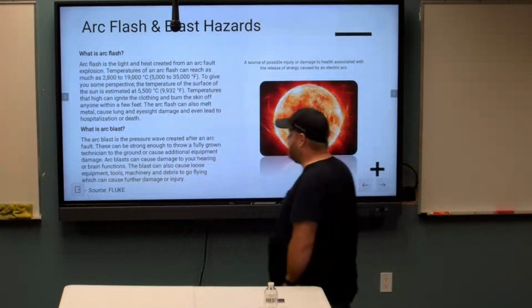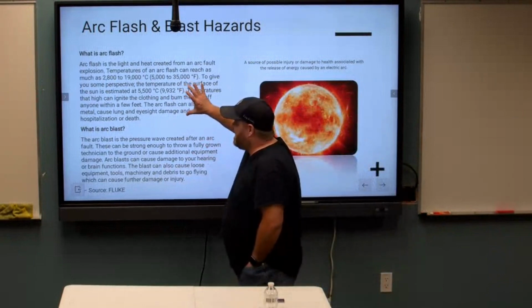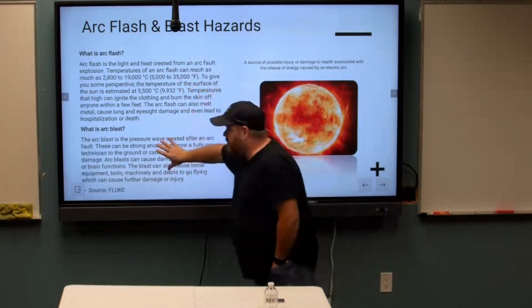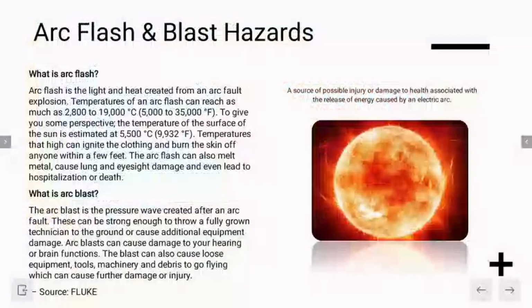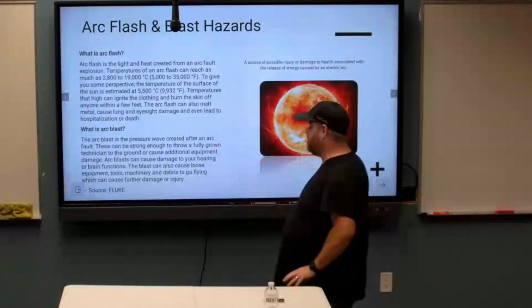All right. So what's an arc blast? The arc flash is the heat and the light. Make sense? Followed by a shock wave called an arc blast. The arc blast is a pressure wave or a shock wave created after the arc fault. Now, arc blasts can be strong enough to throw a fully grown technician to the ground or cause additional equipment damage. Arc blasts alone, just the shock wave alone, can crush bones. It can destroy vital organs in your body. And you don't even have to be right at the point of work. You can be a few feet away and it can blow you away. So we're going to talk about the boundaries related to arc flash and shock, okay? Because there are boundaries we have to maintain for both of these hazards.